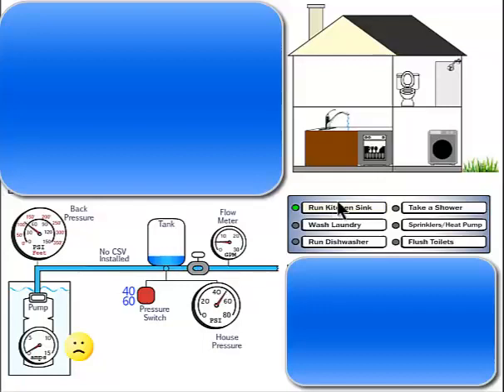So when you open a faucet, the pressure will drop from 60 to 40 PSI as the diaphragm pushes the water out of the tank. At 40 PSI, the tank is empty and the pressure switch starts the pump. The pump is producing 25 gallons per minute and the faucet is only using 5 gallons per minute. So the extra 20 gallons per minute produced by the pump goes into the pressure tank until it is full and up to 60 PSI where the pressure switch shuts the pump off.